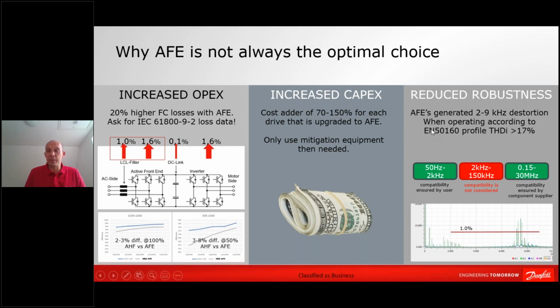And then last but not least, if you are applying AFE drives in general, you should be aware of your grid conditions, because for some AFEs, if you're loading that with standard load profiles from the EN standard, you will see that the current distortion is actually not 5%, it's probably somewhere around 17%. So 5% is, yes, that's correct, or 3% some even claim, and that's perfect for a perfect network. But the more distorted the network is getting, the worse the performance of the AFE is also getting.